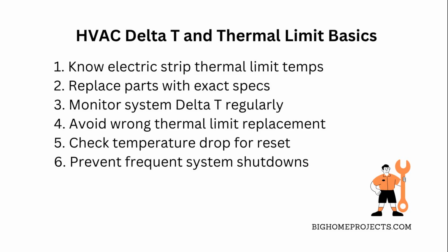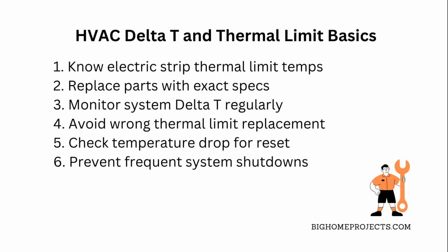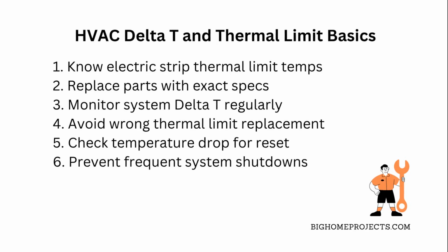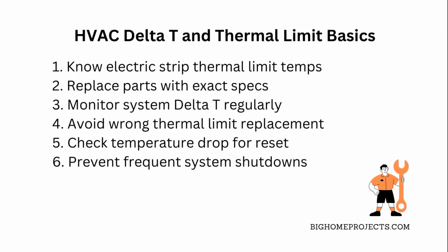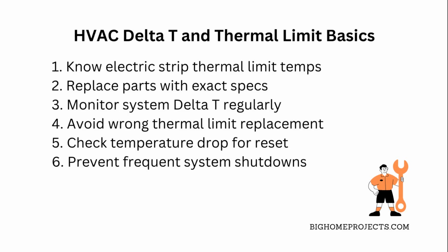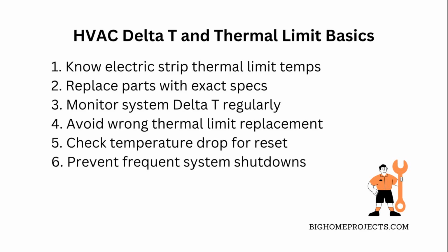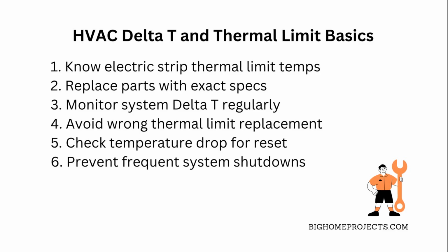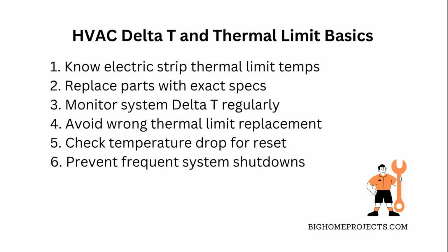These limits are designed to open when things get too hot, stopping the electric strip from burning out or causing damage. Once they trip, they don't reset until the temperature cools down by around 40 degrees, so they close back up at about 105 degrees Fahrenheit. That delay keeps the system safe and prevents it from cycling on and off too fast, which can mess things up. If you're replacing these parts, make sure you get the exact thermal limit specs. Don't just grab whatever looks similar, because even small differences can cause issues.